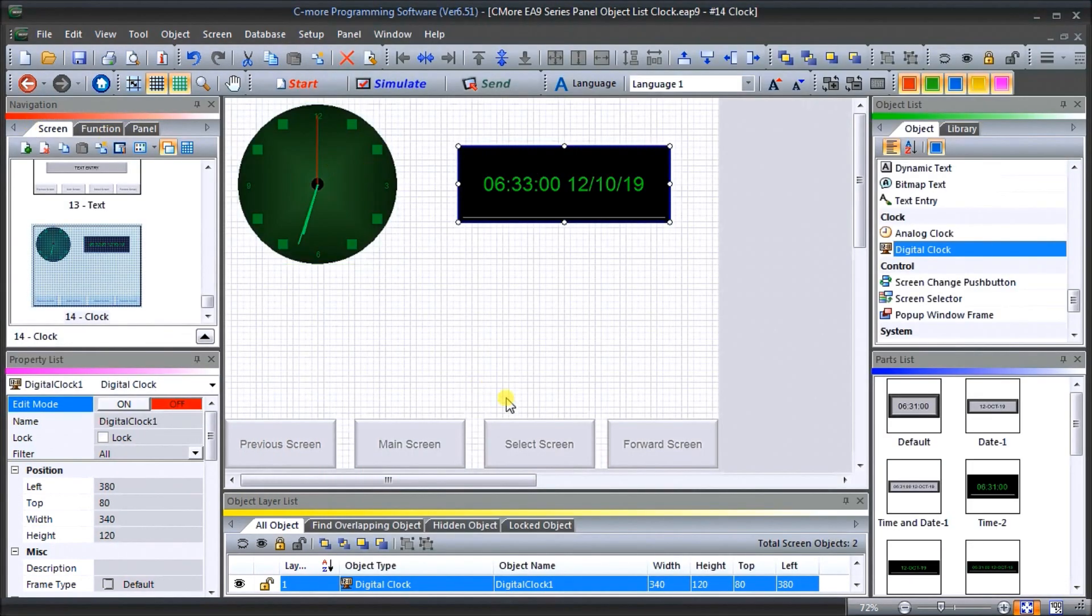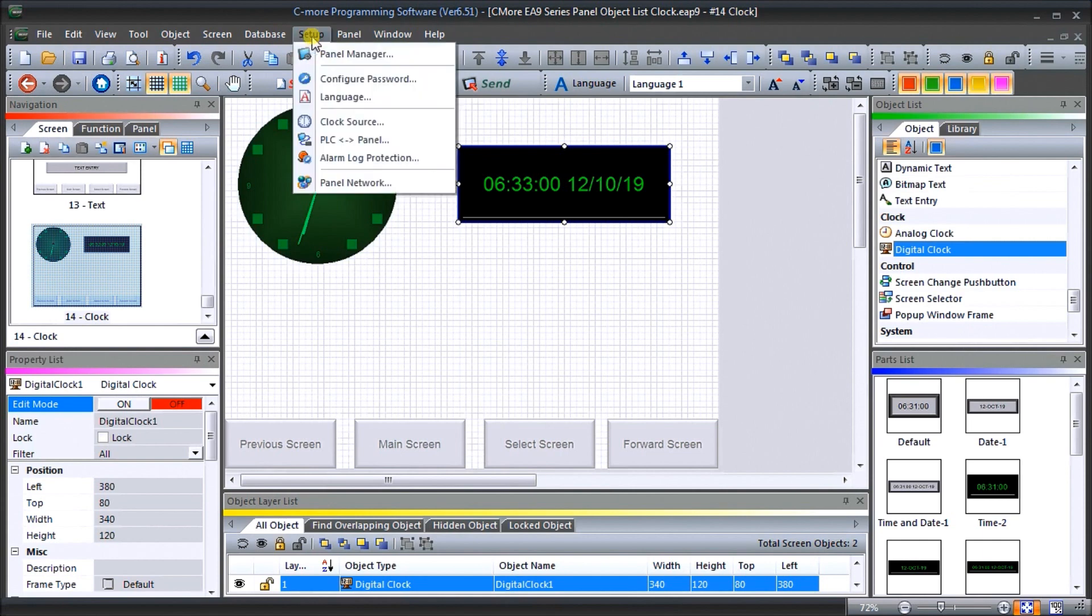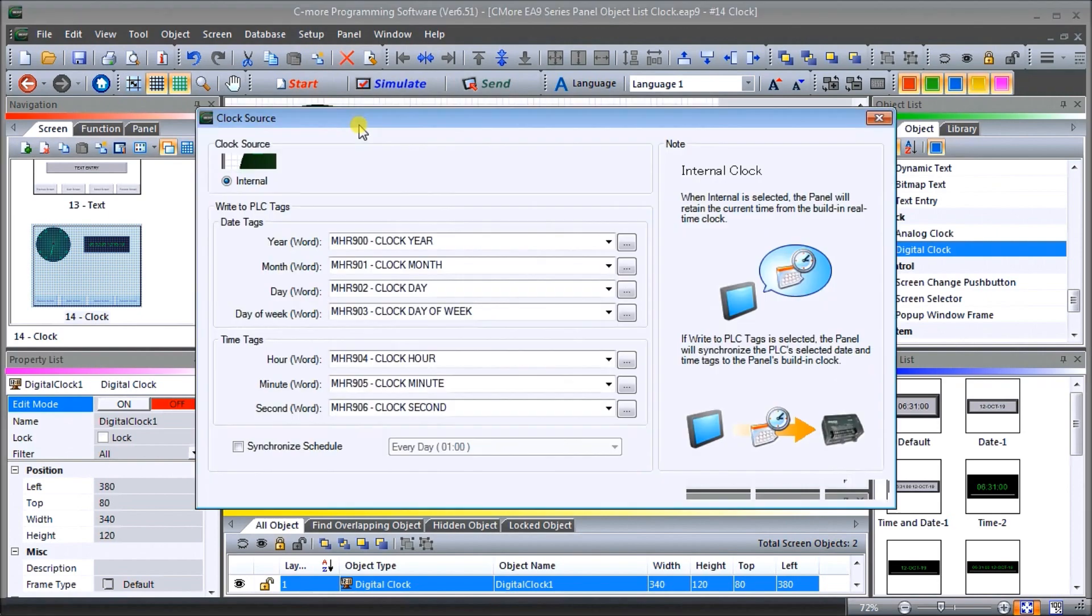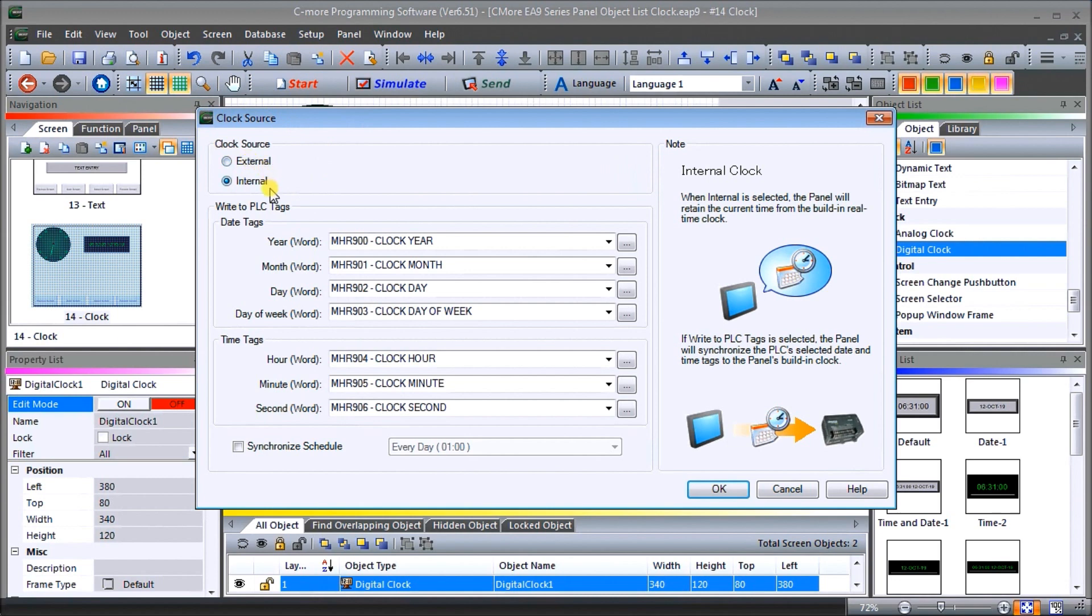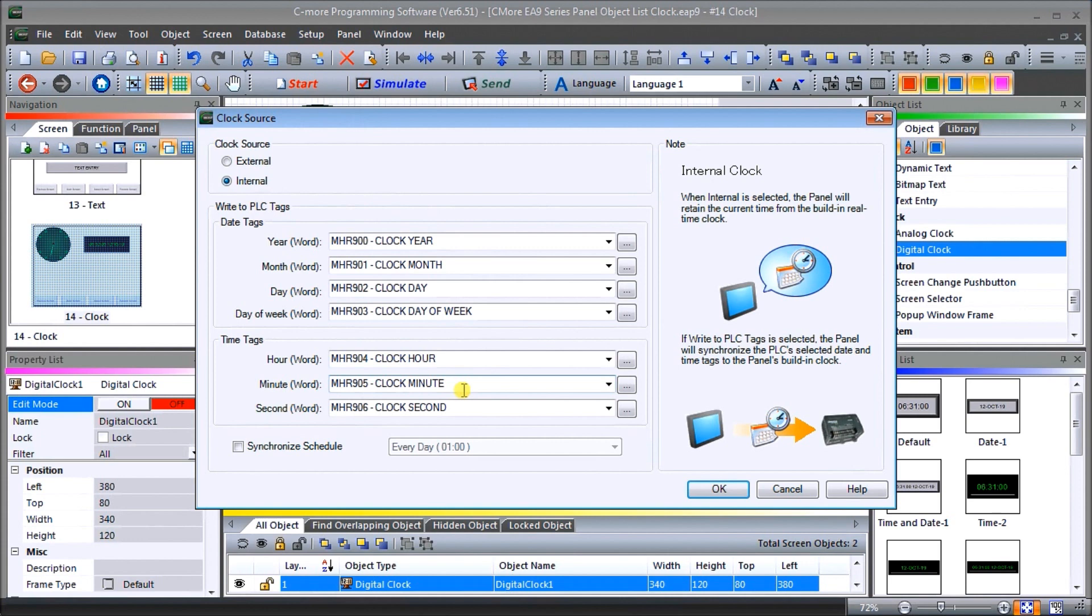What we can do now is we can look under the setup, and under this clock setup we have clock source. Under source what we have is either a clock source of internal or external. When it's internal, then what happens is the HMI will use the internal real time clock as a source for the date and time. If we want to, which we have in here, we've actually set our tags to actually write to these individual tags in the PLC. When it writes the tags in the PLC, then it's actually writing the current time and date into that PLC so we can use that in our program. So it syncs those two sources of real time clocks.